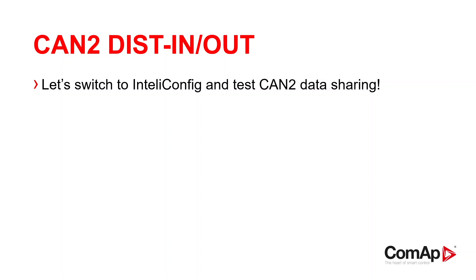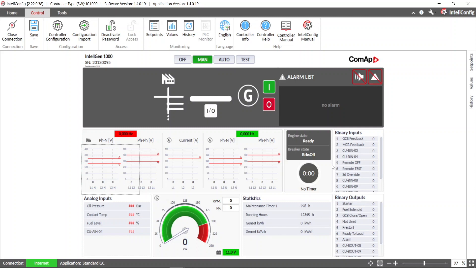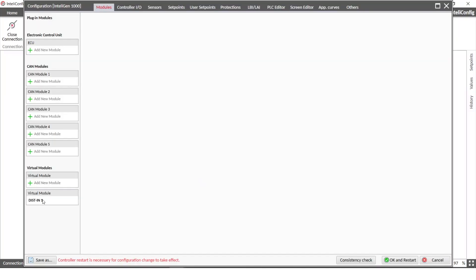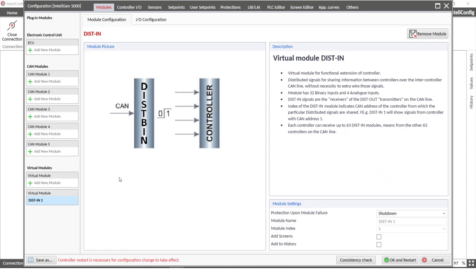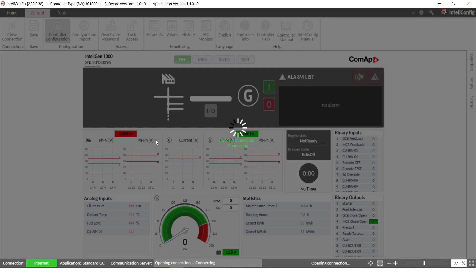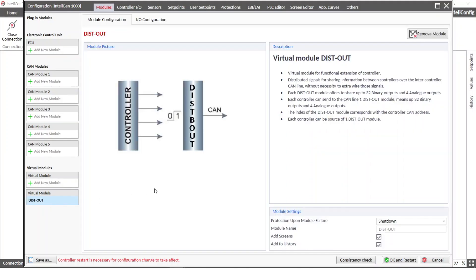Now let's switch to InteliConfig and test CAN2 data sharing. Here I have two InteliGen 1000 controllers that are interconnected over the CAN2a and also CAN2b intercontroller communication lines. I have already configured the virtual dist.out and dist.in modules in both of those controllers. This is the dist.in module for inputs with module index 1, and on the second controller I have the dist.out module with the index that corresponds with the controller address.